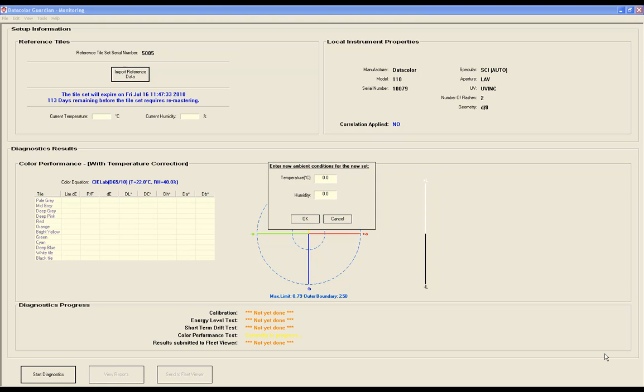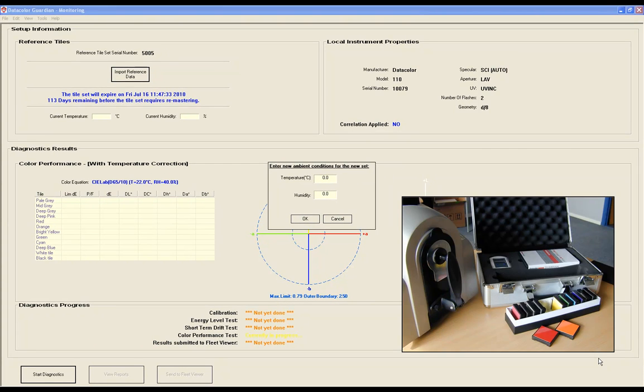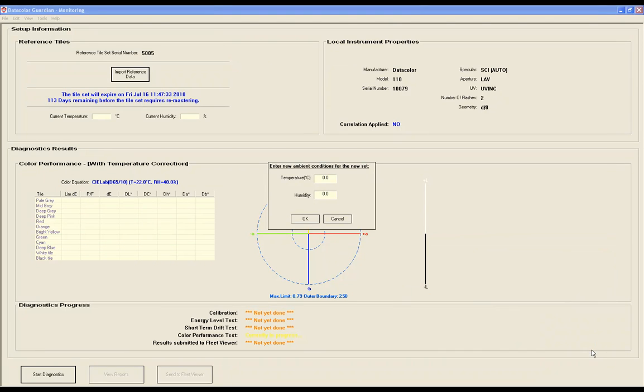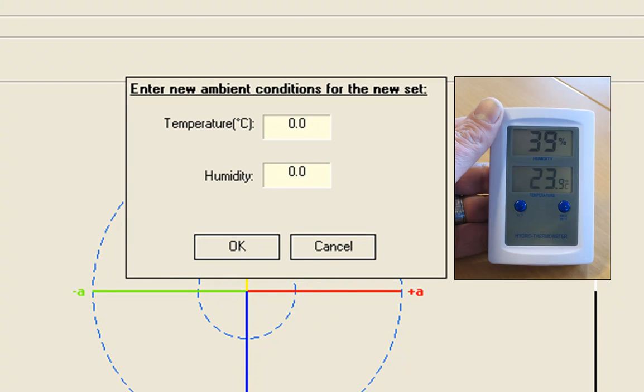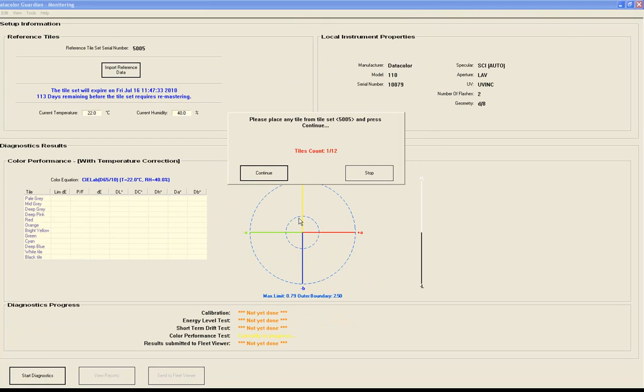After this test, the last test and the most important test is the color performance check. For the color performance test, we need the tile set in the Guardian case. This test will measure the 12 colored tiles. The first thing to do is to enter temperature and humidity that can be obtained from the device present in the Guardian case. So here we fill in temperature is 22 degrees and humidity is 40%, and we hit the OK button.